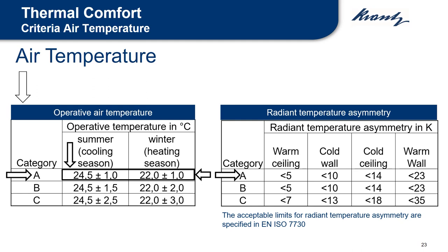According to DIN EN ISO 7730, the asymmetry of radiation for the warm or cold ceiling is related to a horizontal surface element and for the warm or cold wall to a vertical surface element. With the assumption that only one thermally active component is in radiation exchange with a person, the mean radiation temperature is calculated for each of 2 fictitious half-rooms. The difference between these 2 mean radiation temperatures is the asymmetry of radiation. The value determined for the asymmetry of radiation is then compared with the values recommended in DIN EN ISO 7730, and thus the category A, B or C for thermal comfort is determined.